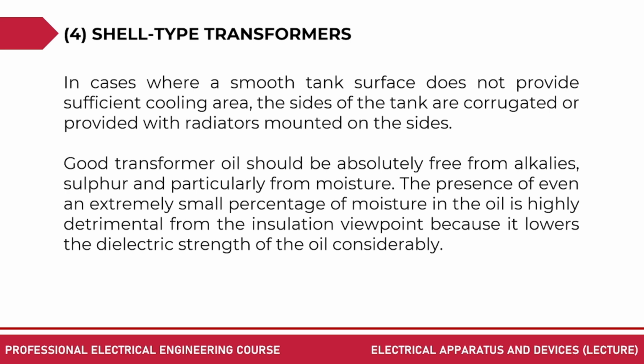In cases where a smooth tank surface does not provide sufficient cooling area, the sides of the tank are corrugated or provided with radiators mounted on the sides. Good transformer oil should be absolutely free from alkalis, sulfur, and particularly from moisture. The presence of even an extremely small percentage of moisture in the oil is highly detrimental from the insulation viewpoint because it lowers the dielectric strength of the oil considerably.